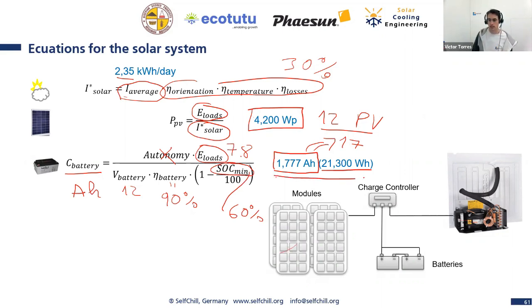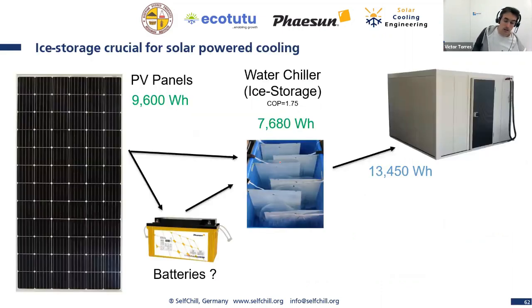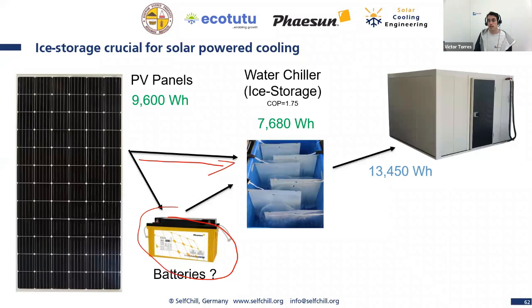We will need 1,700 amperes hour. Now let's look at our thermal storage, because what we can do is we don't need to store the whole energy in the batteries. We can actually deliver energy directly to the water chiller, to our ice storage, and then save the energy there in the form of ice. We have the option open - we can have bigger batteries, or more or less cooling units. Now let's look at how we deal with this.